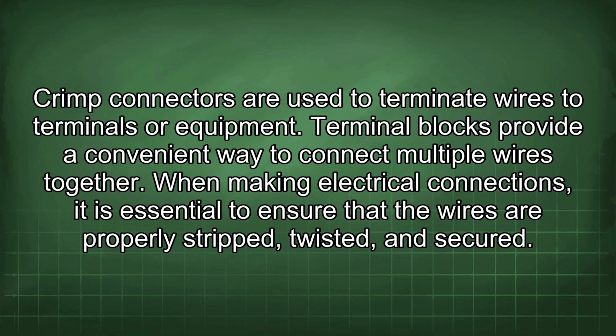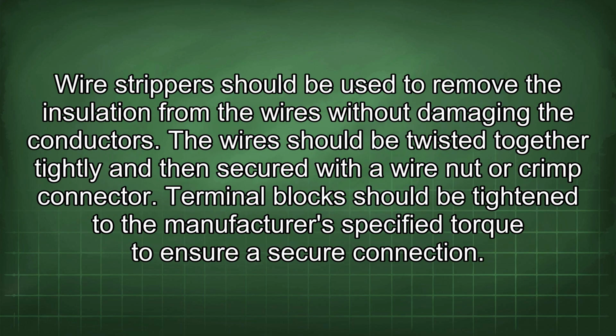When making electrical connections, it is essential to ensure that the wires are properly stripped, twisted, and secured. Wire strippers should be used to remove the insulation from the wires without damaging the conductors. The wires should be twisted together tightly and then secured with a wire nut or crimp connector. Terminal blocks should be tightened to the manufacturer's specified torque to ensure a secure connection.